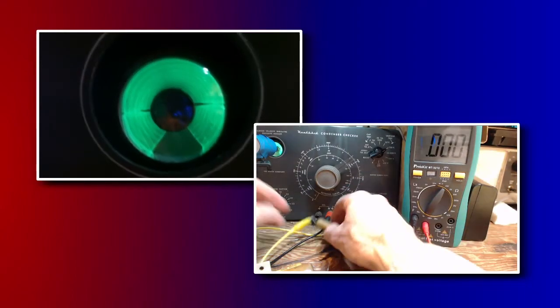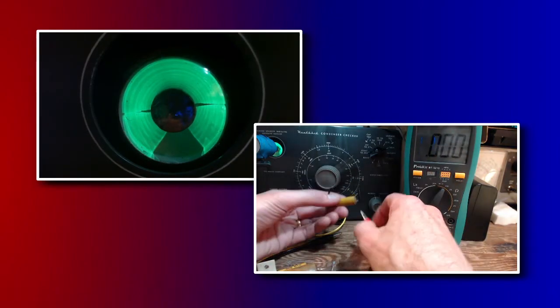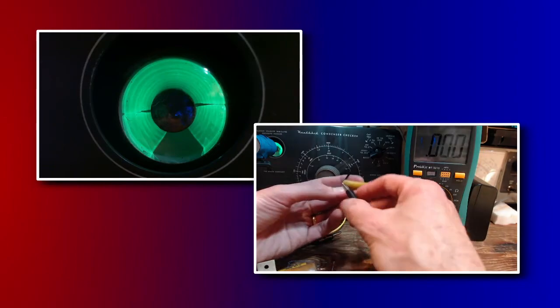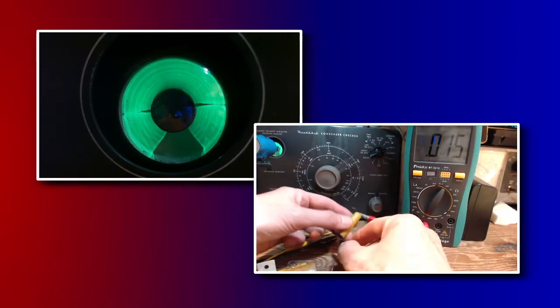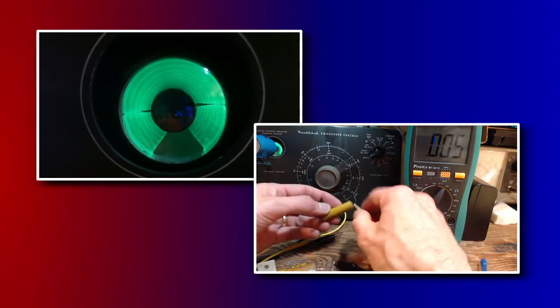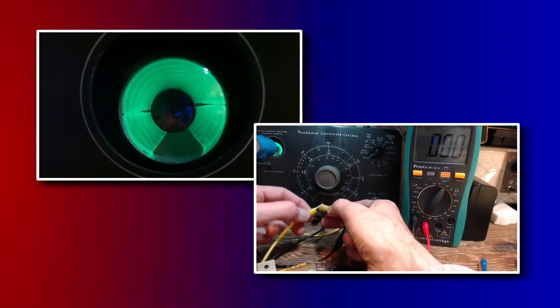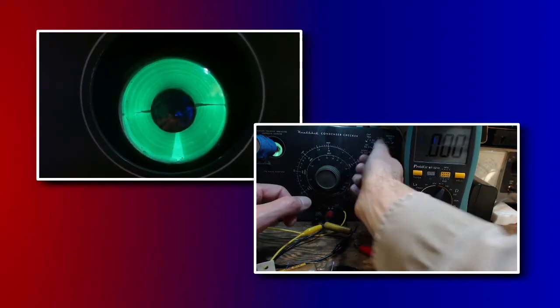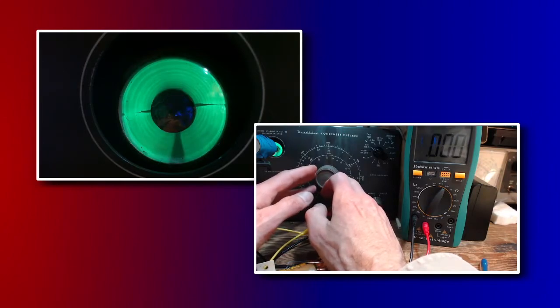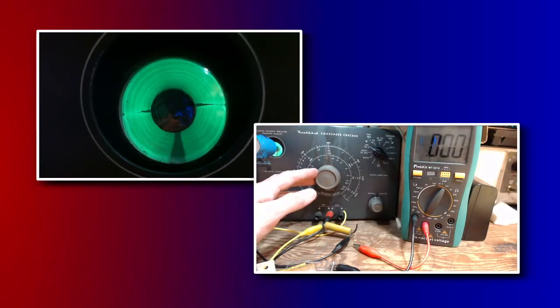And now we're down to the last one. This one is a 0.02. Okay, so on the digital meter, 0.018. It's exactly the same as the last time. .02 is going to be in here. .02 should be right up in here. Look at that, it's coming out correct. It's not opening fully though. Bang on. It's right on. 0.02. Same reading as last time.